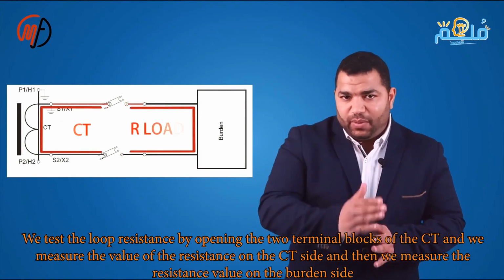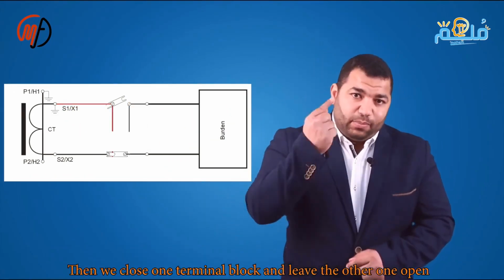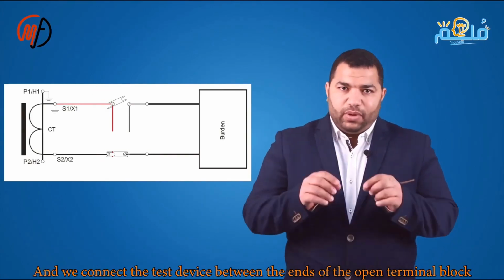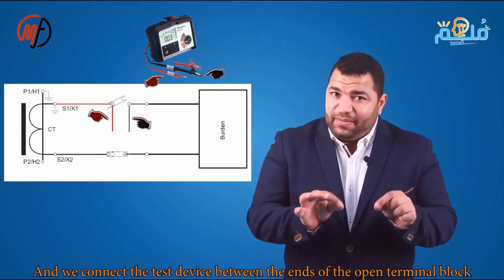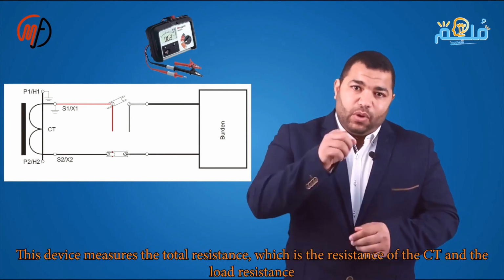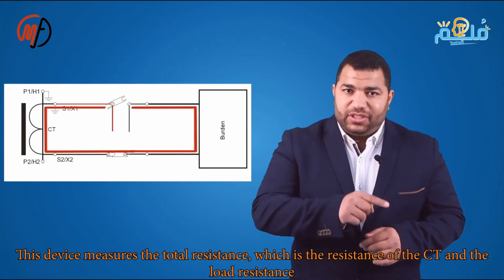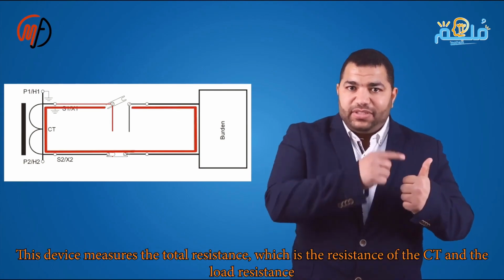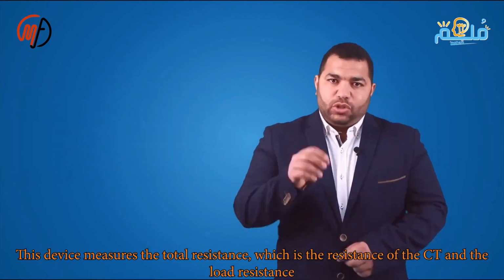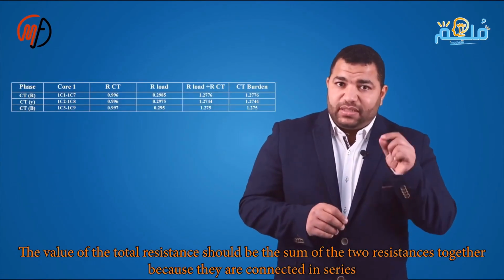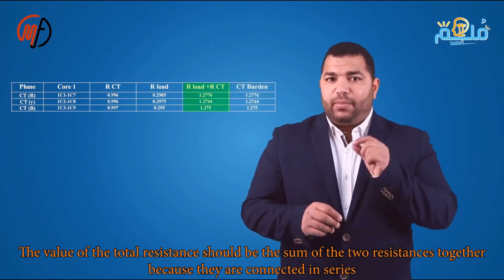We keep one terminal block closed and open the other. Then we place the testing device between the open terminal block ends. This device measures the total resistance between the open terminal block ends, which includes the CT and burden resistances. The total loop resistance is the sum of the CT side and burden side resistances measured earlier, as they are in series: loop resistance equals CT resistance plus load resistance plus wiring resistance.